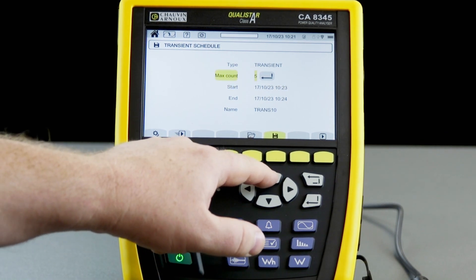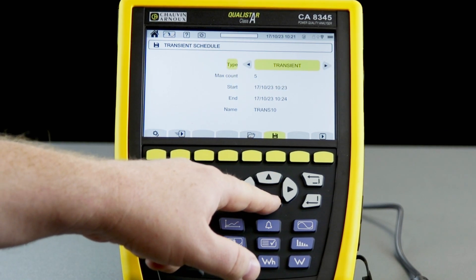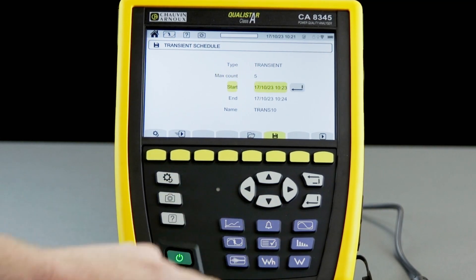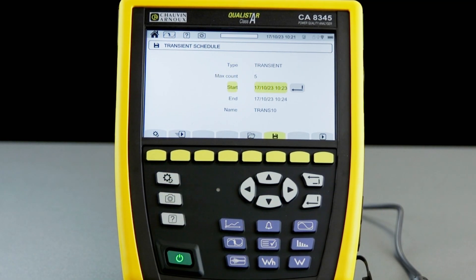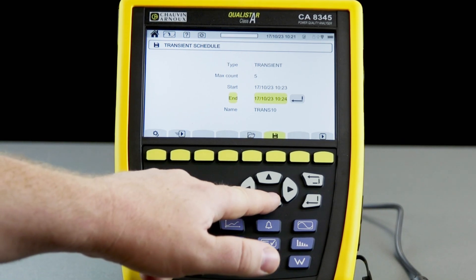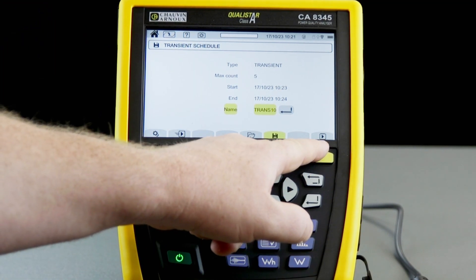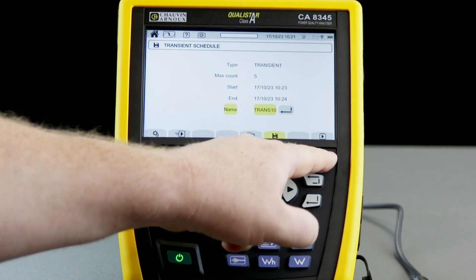In here we can set up a transient logging event. It asks us what we're looking for — in this case transients — and how many transients we want to record during the session, which I've set to five. We also set when we want to start and end the session, and what we want to call the session. Once we've set these parameters and the CA-8345 is happy with them, we can start the session by pressing the play icon.